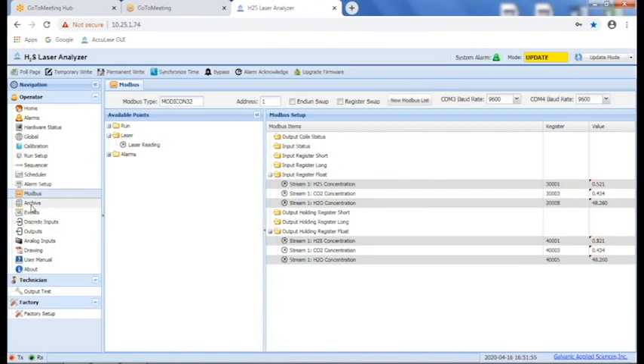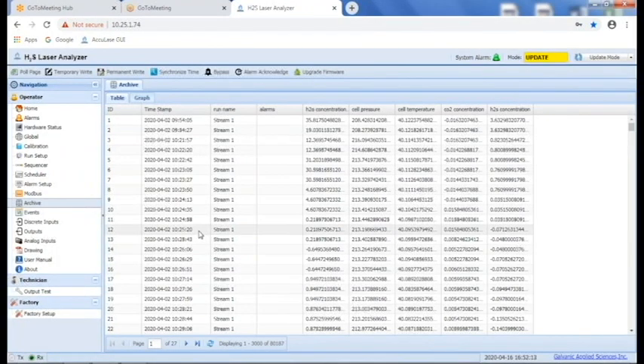The archive gives you a running history of the analyzer. Basically every time it makes a measurement, it logs it. It's a tremendous amount of information, but it allows you to go back in time many days, typically about a month. It logs which stream ran, if there were any alarms, the H2O concentration, the cell pressure, cell temperature, CO2 concentration, and the H2S concentration. In this way, you can correlate between pressure, temperature, and the readings.